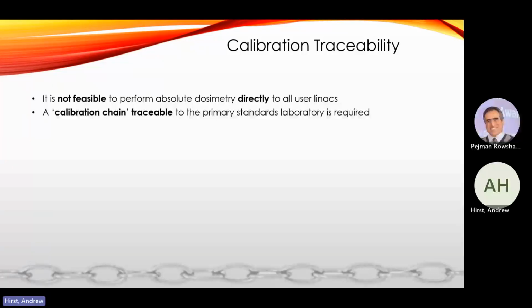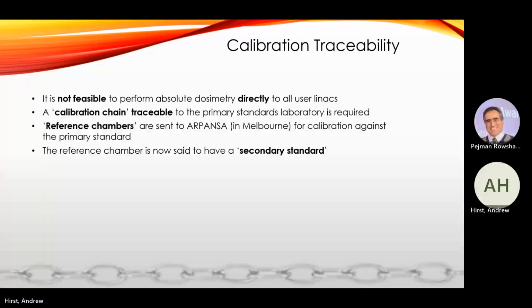Calibration traceability. It's not feasible to perform the absolute dosimetry directly to all user linacs. So we can't get that graphite calorimeter, bring it over to our linac, model our linac on a Monte Carlo sim, and do all that kind of stuff. So what we do is we have a calibration chain that's traceable from the primary standards lab. And I think you guys have learned about that in the current unit. The kind of terminology we use is the reference chamber is the one we send to ARPANSA, which is in Melbourne, for calibration against that primary standard, so the graphite calorimeter.